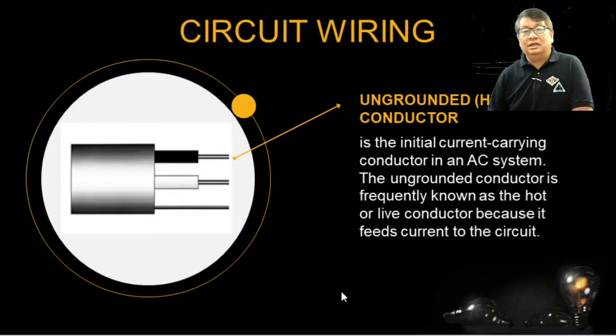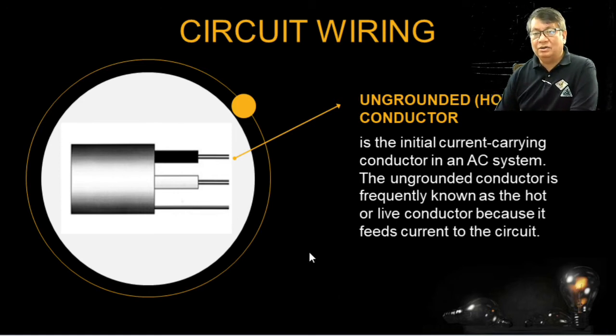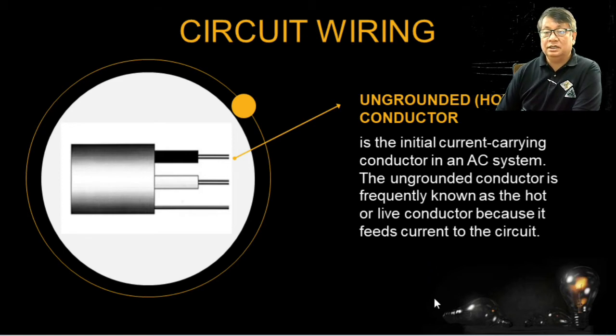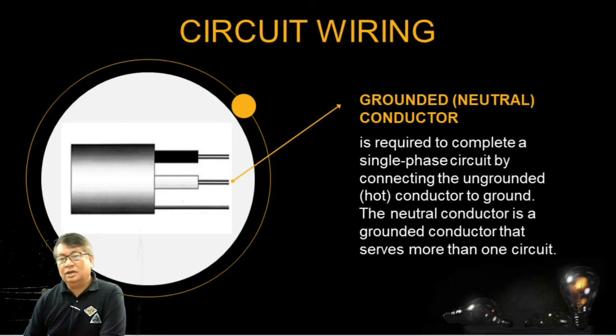So we have this circuit wiring. So ungrounded hot conductor. So mayroon po tayo dito. Okay, it is the initial current carrying conductor in an AC system. The ungrounded conductor is frequently known as the hot or live conductor because it feeds current to the circuit. So the grounded neutral conductor is required to complete a single phase circuit by connecting the ungrounded conductor to ground. Okay, the neutral conductor is a grounded conductor that serves more than one circuit. So maroon po tayo niyan.